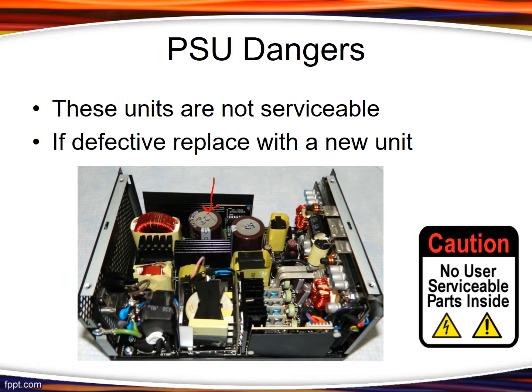There's a fuse in here that's usually soldered to the board. If that fuse blows, it blew for a reason—either the transformer shorted out, or a capacitor shorted out, or a voltage MOSFET or regulator burned up. There's a reason why that fuse blew. We don't open them—you can open them and look if you want to, but don't touch anything in there. When they are defective, we throw them away. They're what we call a non-serviceable part.